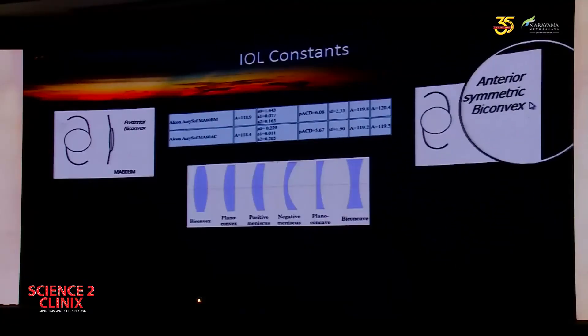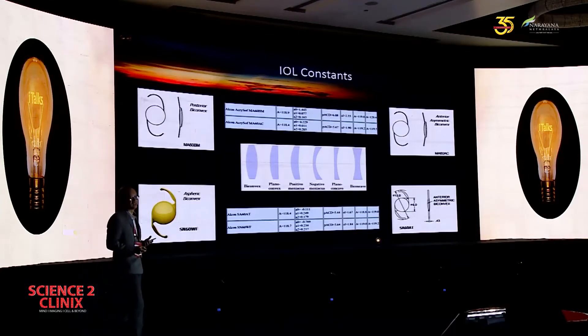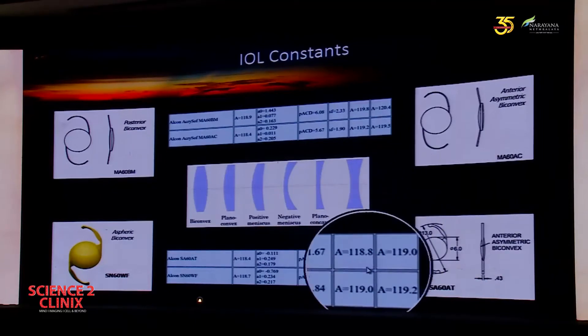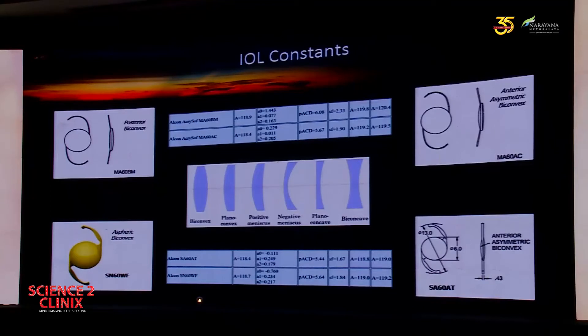For example, the thicker the lens, the A constant actually changes because A constant is something physical and somewhat arbitrary. Another example: aspheric versus non-aspheric. The A constants are 118.8 and 119 — they are similar lenses, but aspheric generally have a higher A constant than non-aspheric, because by design of the spherical aberration, the optical plane is slightly more posterior. Therefore the A constant must be a little bit higher. This essentially explains why different IOLs have different A constants — same IOL with different curvature and different optical design will have different A constants.